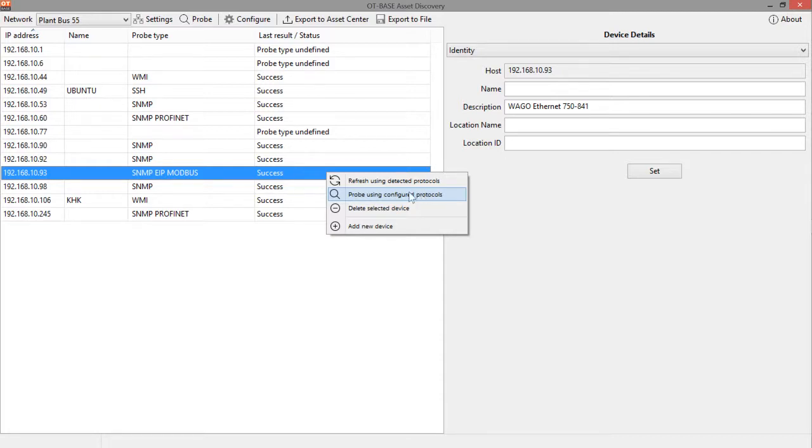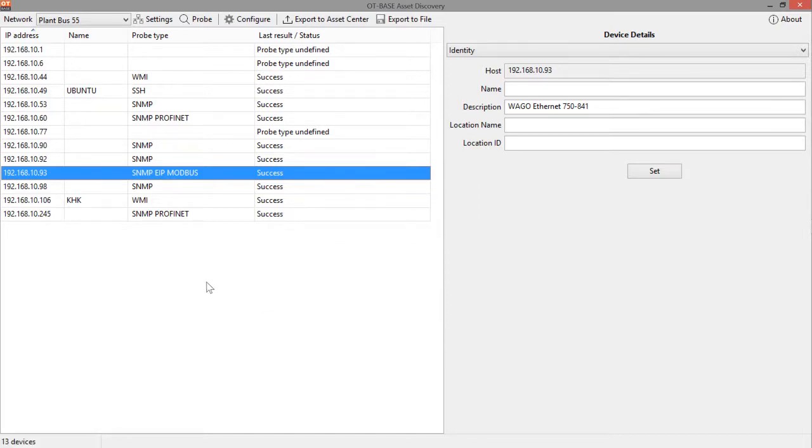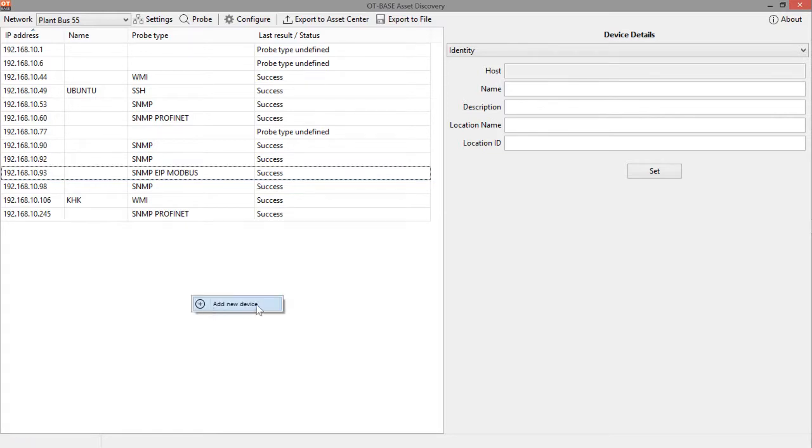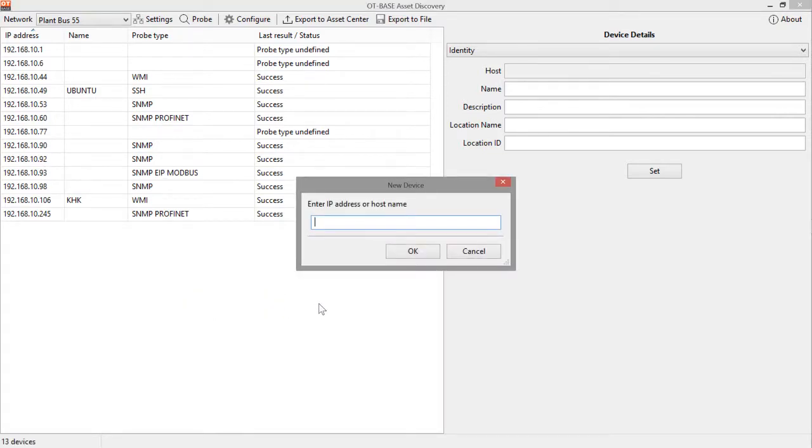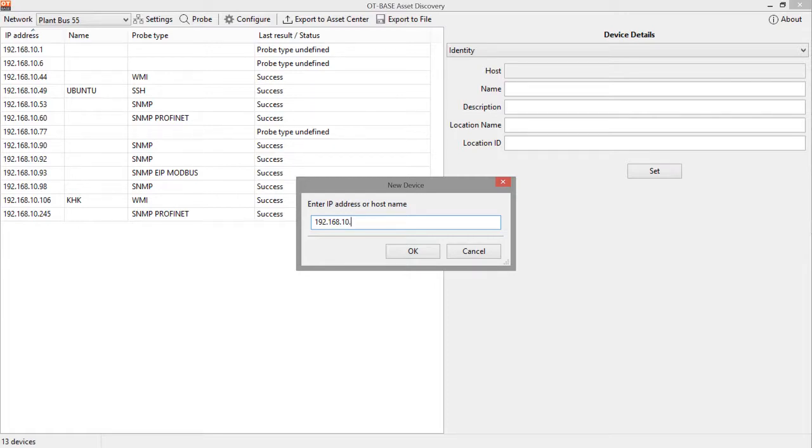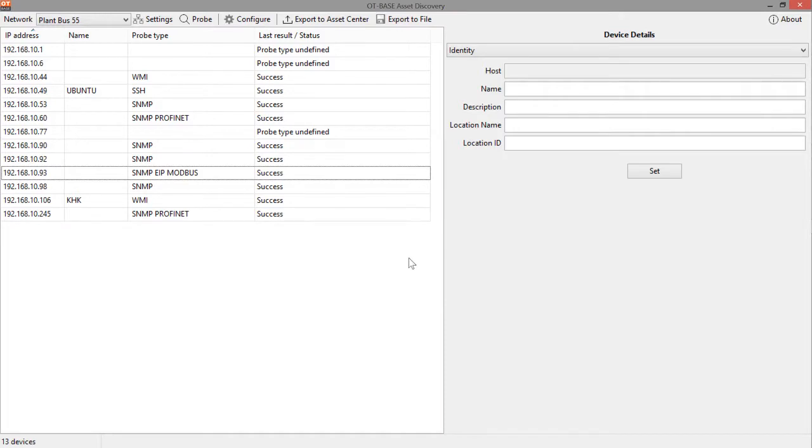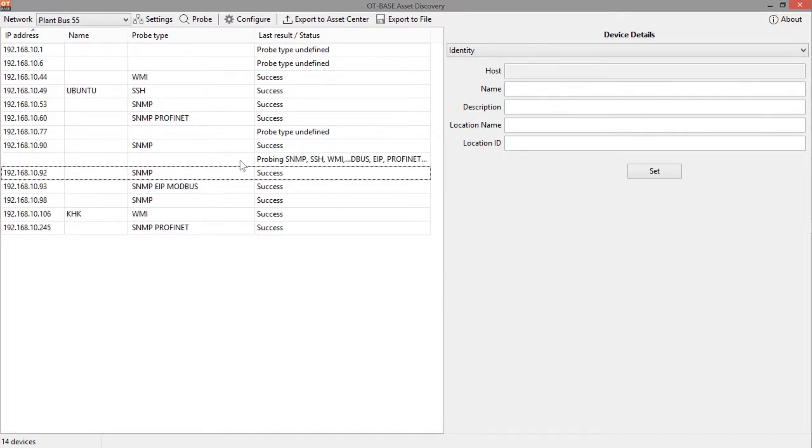And then finally you can add a new device from anywhere. So also in that area down here, where no entries are, you can right click the mouse and add a new device. And here you can specify an IP address. And the purpose of this entry is, let's just assume that you think some device was not properly detected. That can happen, for example, if the device doesn't respond to ARP requests. Then you can just manually input the device right here, click on OK. And then for this new device, OT-based asset discovery will start right away probing that address using all the protocols that have been configured for this network.